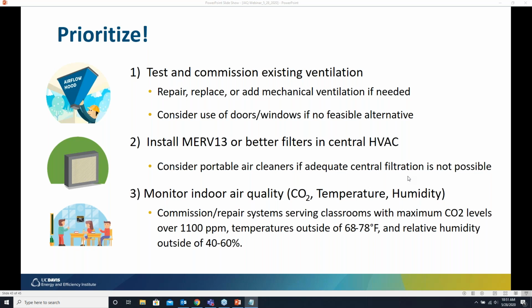And finally, prioritize. So highest priority, test and commission your existing ventilation systems. If needed, repair, replace, or add mechanical ventilation. Consider use of doors and windows as a supplement, or if no feasible alternative. Install MERV 13 or better filters in your central HVAC. Consider portable air cleaners if adequate central filtration is not possible. And then third, monitor indoor air quality, carbon dioxide, temperature, and humidity, and make corrections wherever you notice problems.